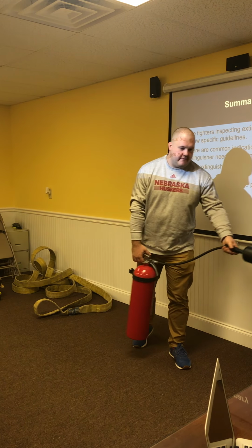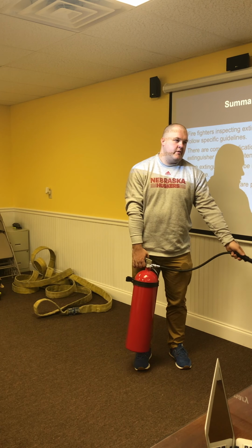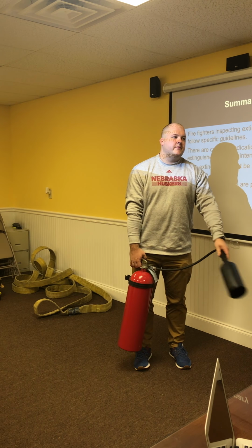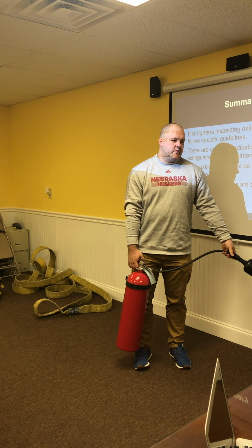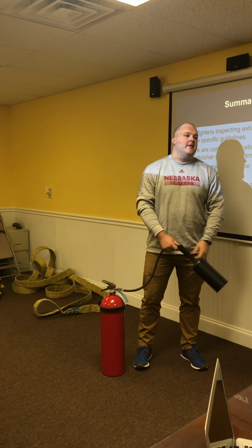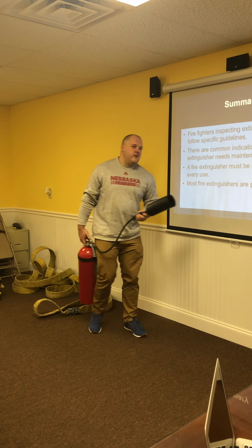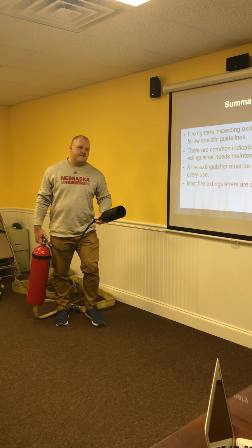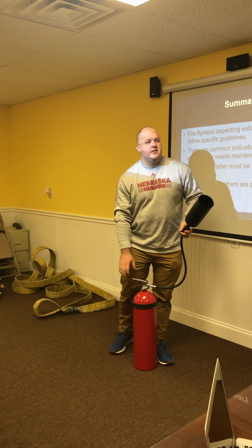He's going to use the PASS acronym at the base of the fire, squeezing the trigger, sweeping side to side at the base of the flames, stopping once the fire is out, and backing away from the fire, obviously facing the fire with the exit behind him. He overhauls the fire to ensure extinguishment, and that concludes that skill.